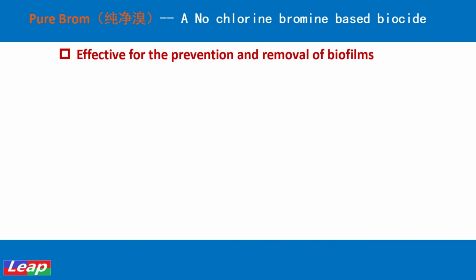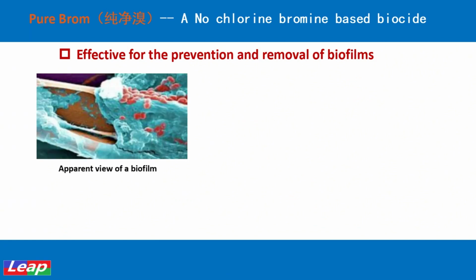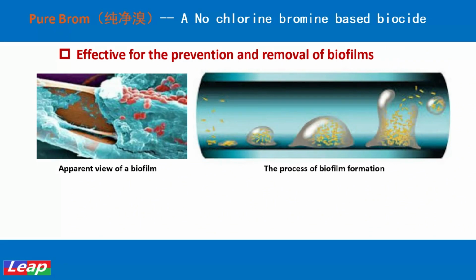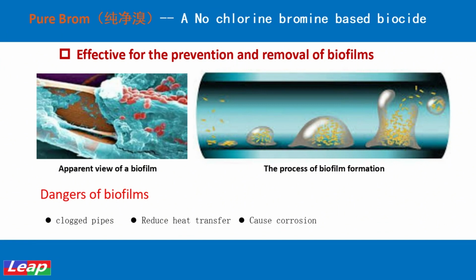of biofilm. Biofilm consists of microorganisms like bacteria, fungi, and algae along with EPS. In water system, most bacterial cells are sessile, forming colonies and biofilm on surfaces. In industrial water system, biofilm formation can cause heat transfer resistance and blockages, leading to issues like MIC and the growth of pathogens like Legionella pneumophila. Thus, biofilm removal and disinfection are crucial for water system maintenance.